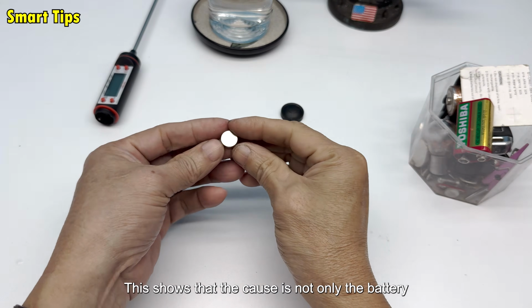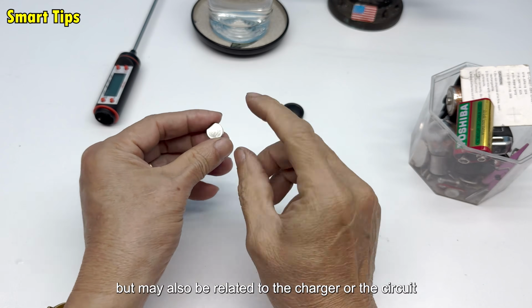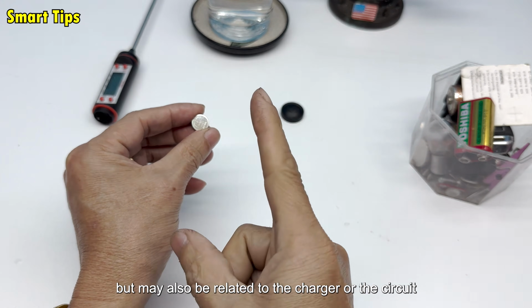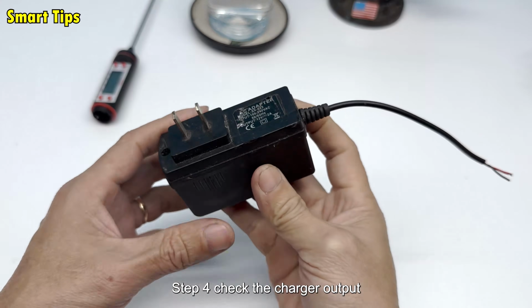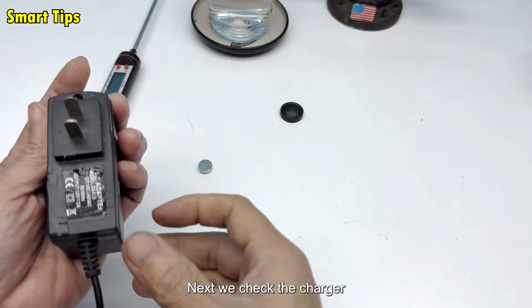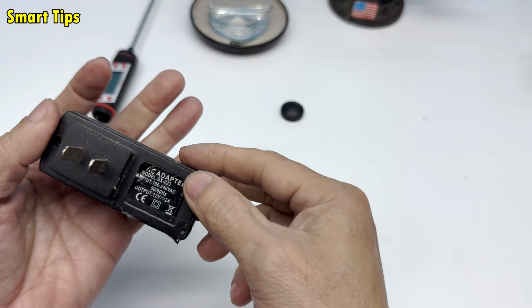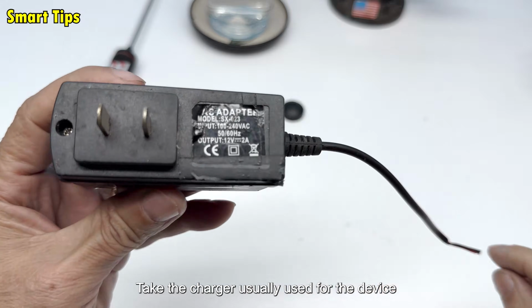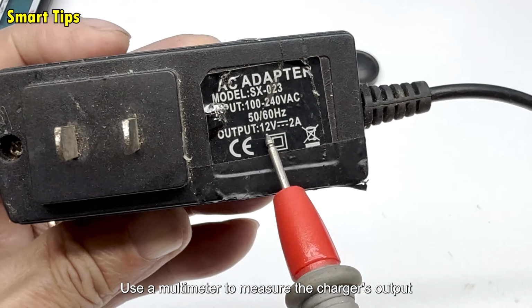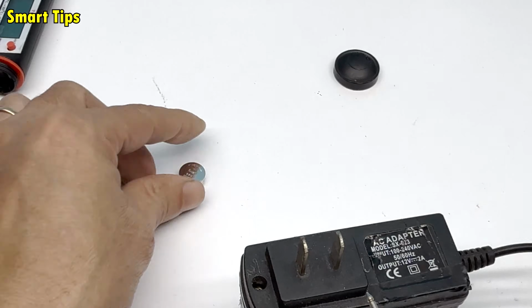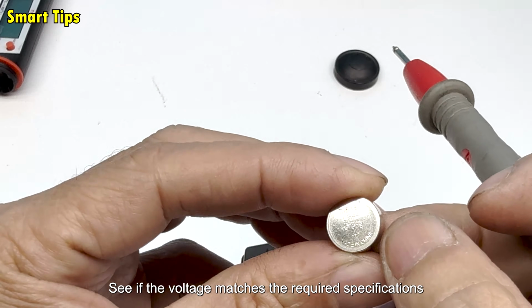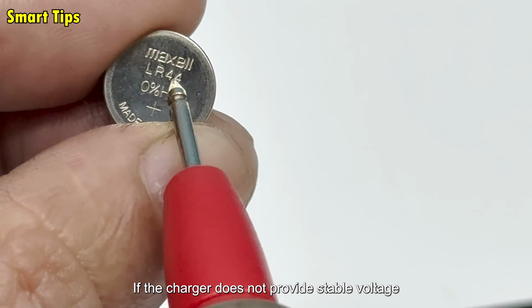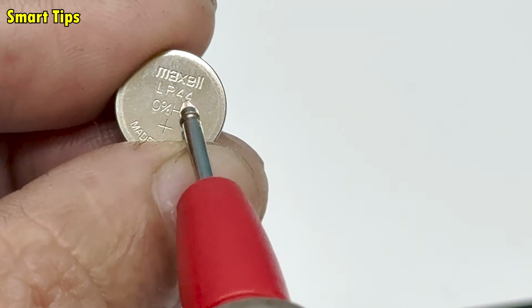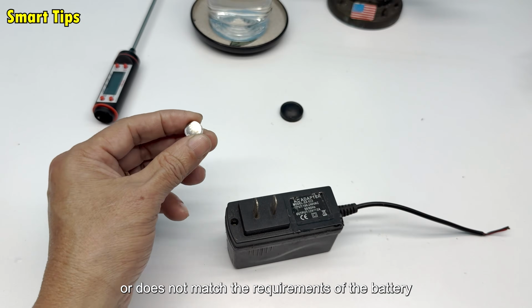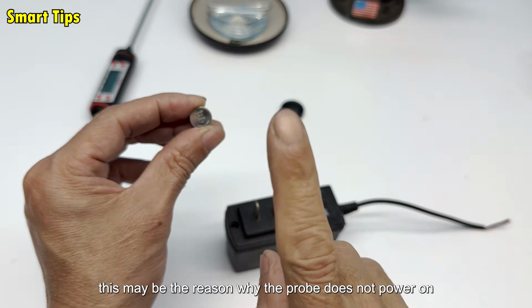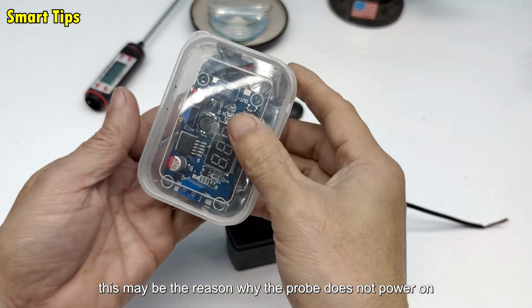This shows that the cause is not only the battery, but may also be related to the charger or the circuit. Step 4. Check the charger output next. We check the charger. Take the charger usually used for the device. Use a multimeter to measure the charger's output. See if the voltage matches the required specifications. If the charger does not provide stable voltage, or does not match the requirements of the battery device, this may be the reason why the probe does not power on.